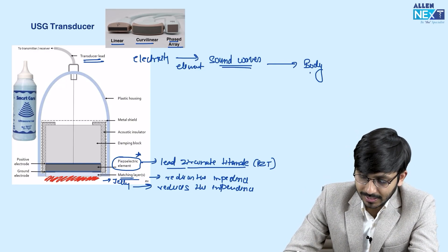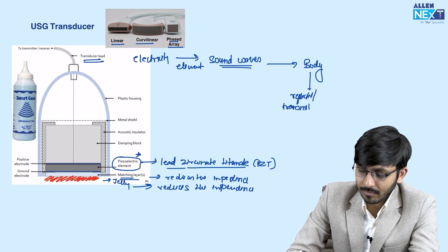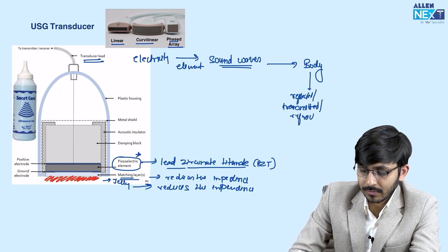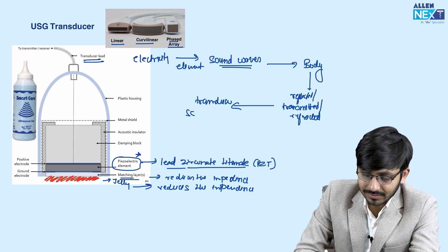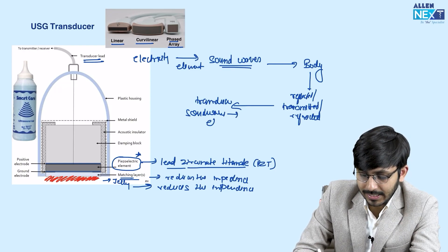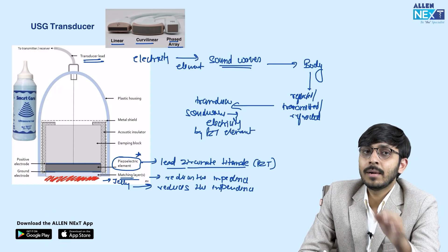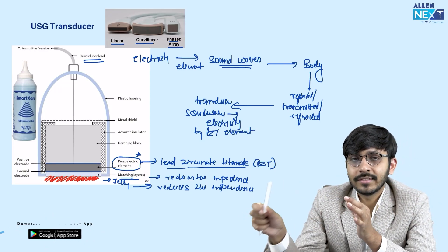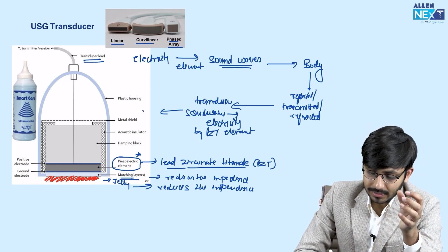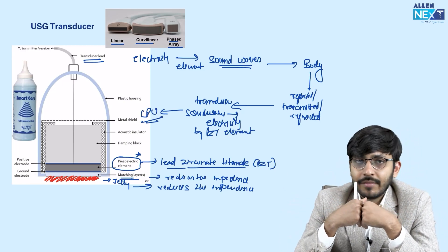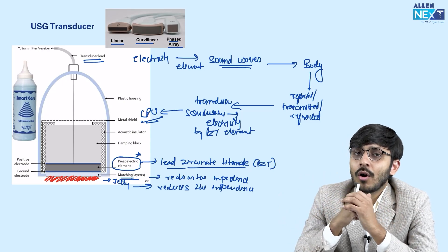Within the body, sound waves travel and are either reflected, transmitted, or refracted. These are again picked up by the same transducer, which converts the sound waves back into electricity via the piezoelectric element. This element works both ways — converting electricity into sound waves and sound waves back into electricity. These electrical signals are then processed by the CPU and converted into the relevant images we see on the screen. This is how the ultrasound transducer is the backbone of the ultrasound machine.